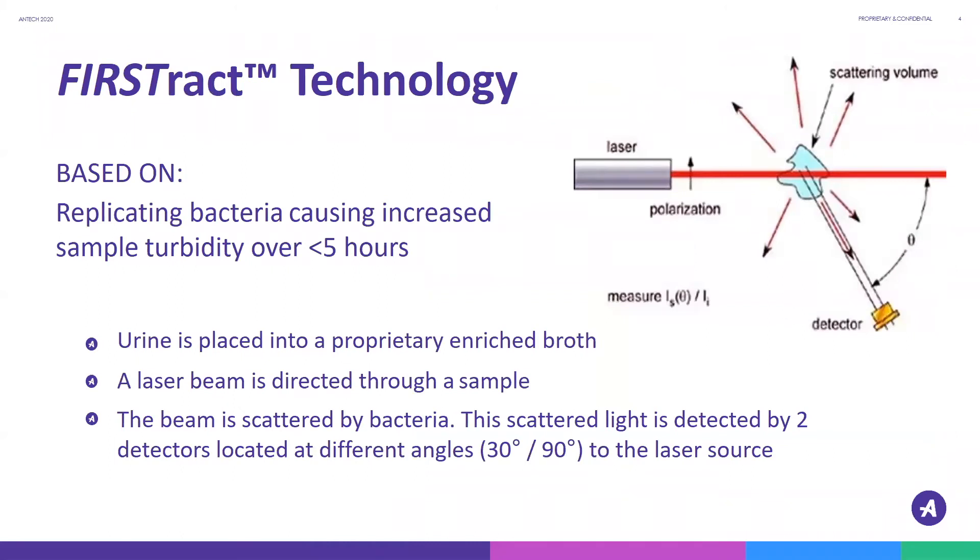FIRSTract uses urine that is placed into a proprietary enriched broth, and then light scattering technology is used to determine if bacteria are present in the sample. A light beam is directed through the sample and is scattered by bacteria if bacteria are actually present. This scattered light is then collected by two detectors located at different angles to the laser beam source.